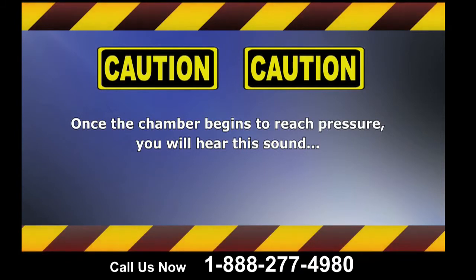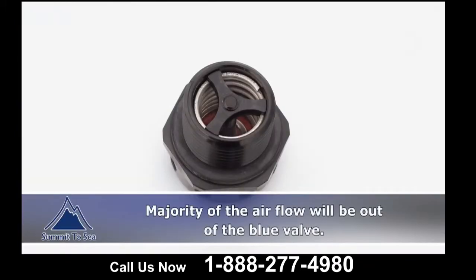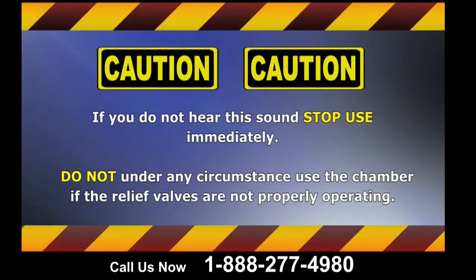This is normal. The sounds you are hearing are the relief valves cycling old air out of the chamber while the compressor cycles new air in. This maintains a constant pressure inside the chamber. If you do not hear this sound and the chamber has been running for more than 10 minutes, immediately end the treatment and call the distributor before further use. Do not, under any circumstance, use the chamber if the relief valves are not properly operating.